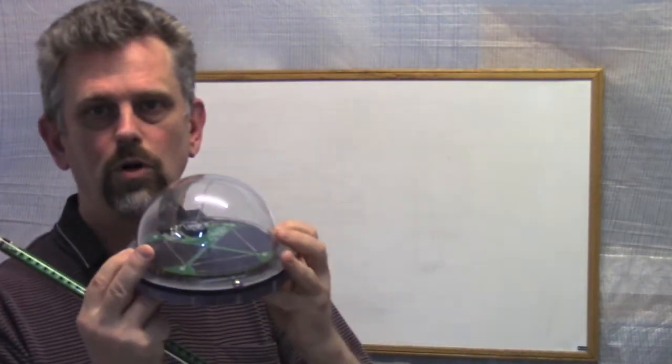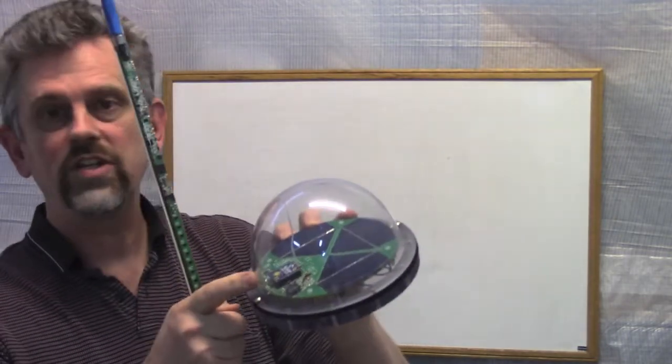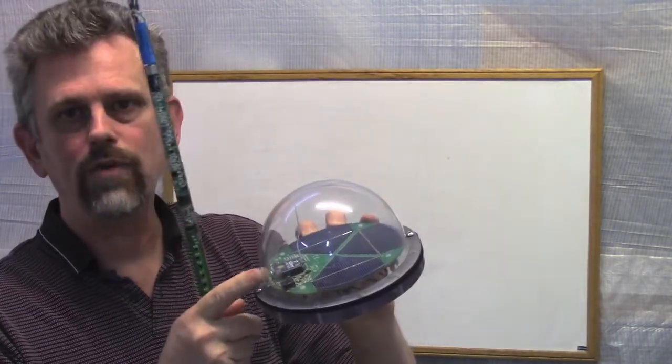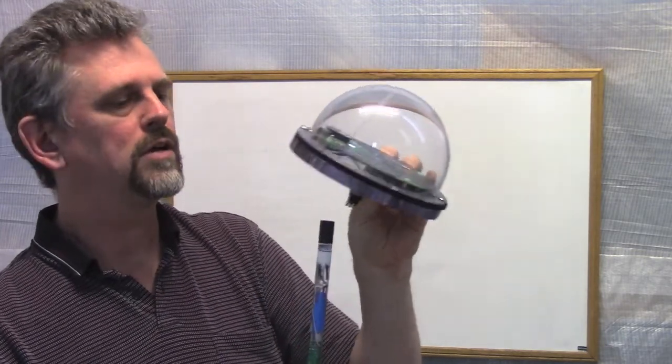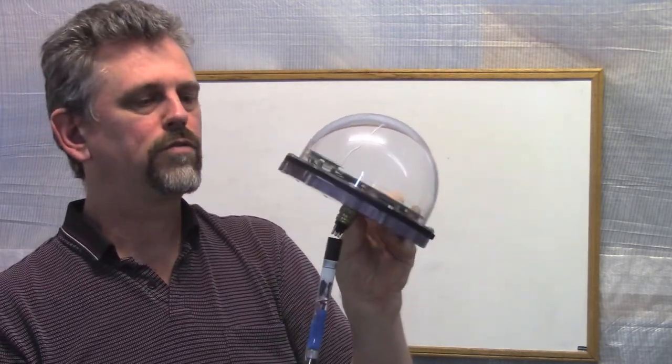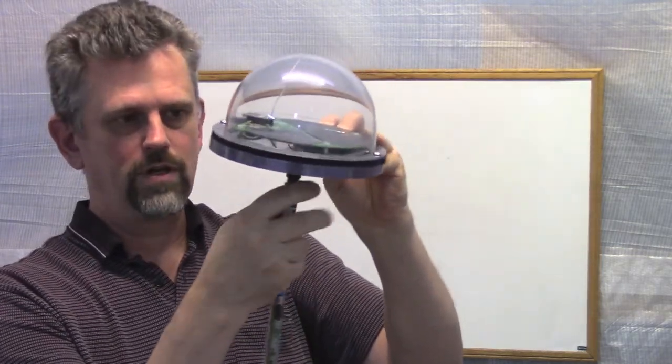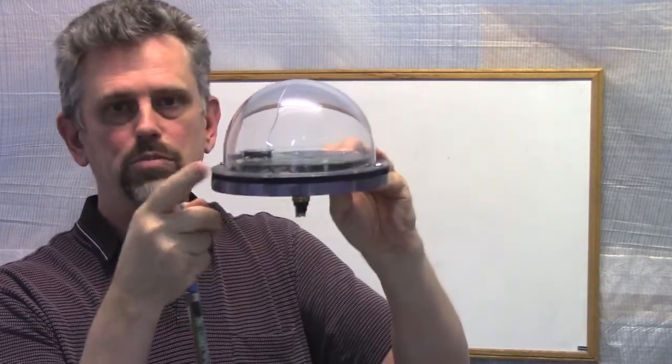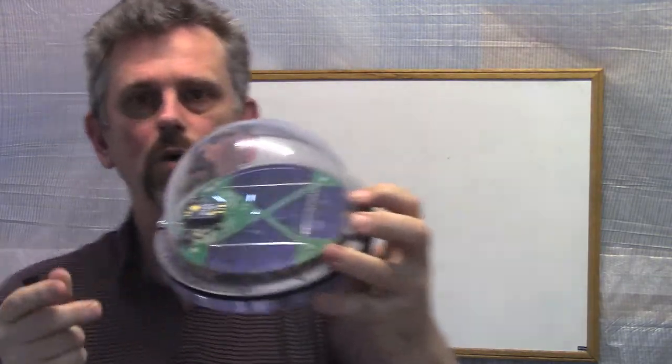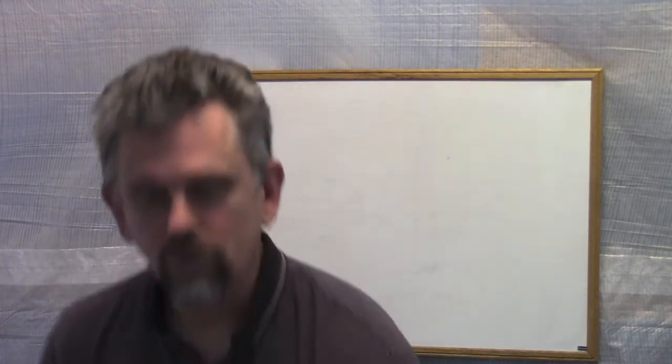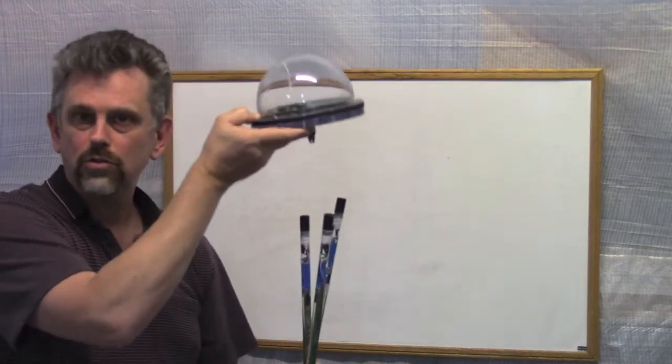Or it can be connected to this radio modem. It's a little radio sitting in here. It's a plug-in radio so it can be changed depending on what part of the world you are and what radio frequencies are allowed. It connects directly onto the Sedimeter, but of course you would put a cable between. Normally I put this on a buoy. This has a solar panel built in. So it charges itself and it charges the Sedimeter. And in fact you could connect three Sedimeters maybe to this.